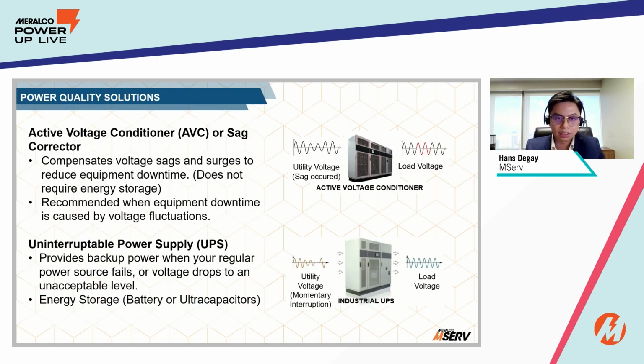So dito naman tayo sa largest pie in the power quality problem, which is voltage sag. It is quite difficult to maintain since the grid is open to both internal and external sources, which could cause voltage sags, or more commonly referred to as fluctuations. It should be noted that this distinction between short voltage variation and long voltage variation is always done to determine the appropriate solution. For short voltage variations such as voltage sags, an active power or voltage conditioner can mitigate this. This type of equipment does not have external energy storage and will rely on existing voltage and boost it back up to normal operation levels. This equipment is designed to capture short duration voltage variation that may be damaging already to the equipment, as per SEMI F47 or ITIC tolerance curve, or similar standards that your current equipment are using.